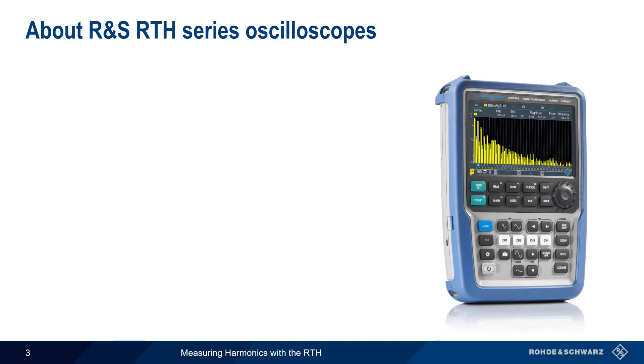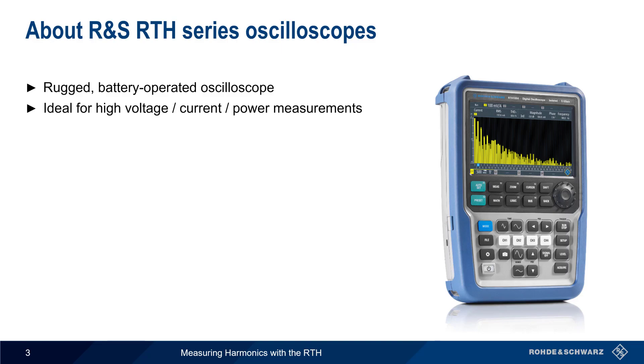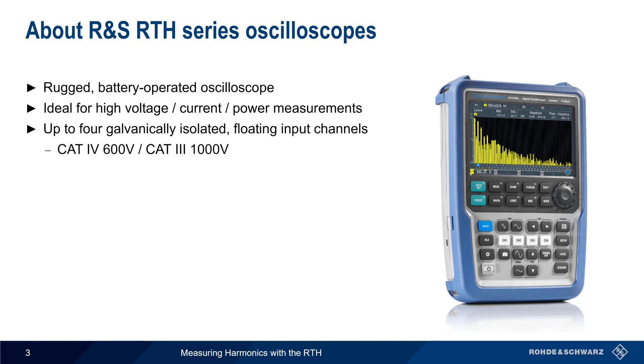Let's start with a brief overview of Rohde & Schwarz RTH Series Oscilloscopes. The RTH is a rugged, battery-powered, general-purpose oscilloscope that also has numerous features and functions that make it ideal for measurements of high voltage, high current, or high power. The scope inputs are all galvanically isolated and floating, with protection of up to 600 volts for Cat4 and 1,000 volts for Cat3. The RTH also offers an offset range of up to 200 volts.